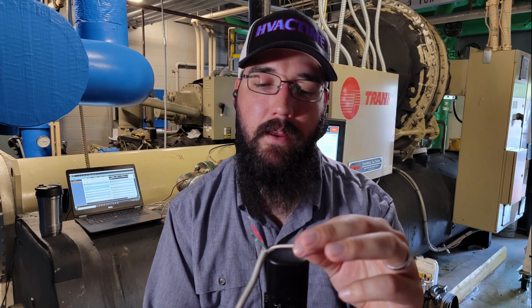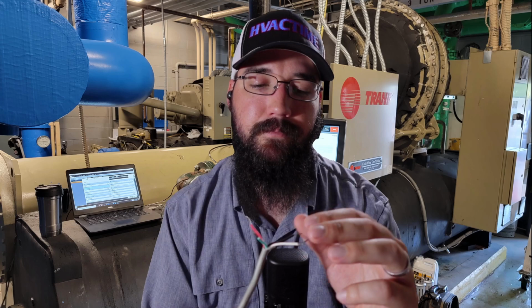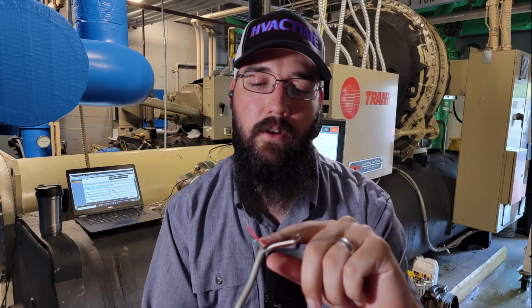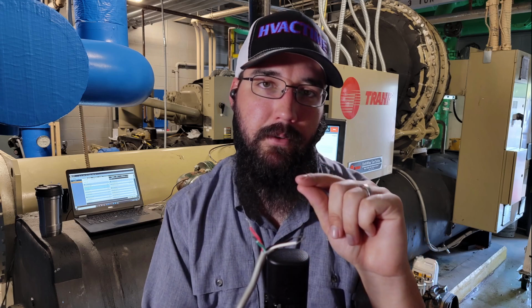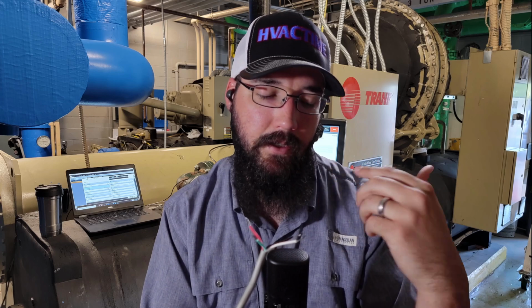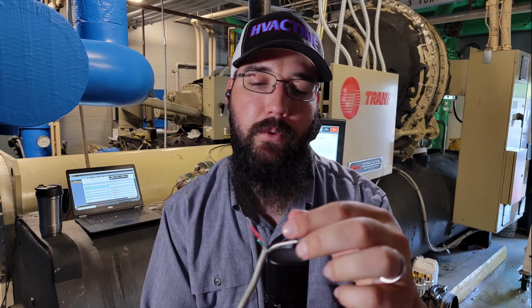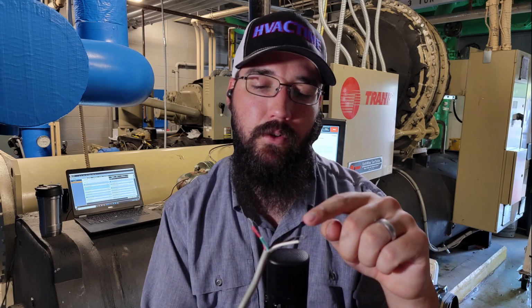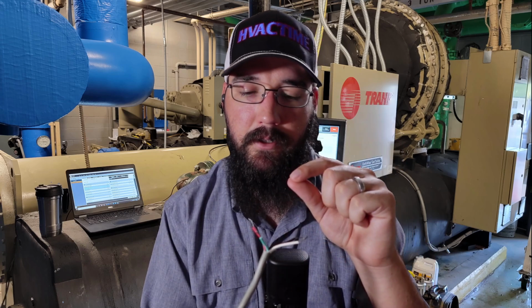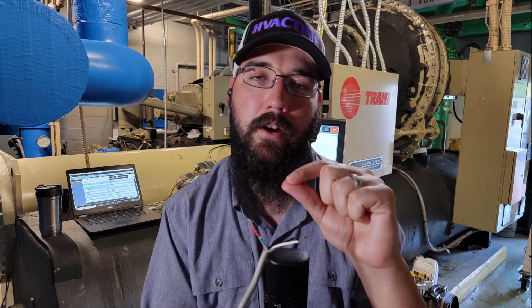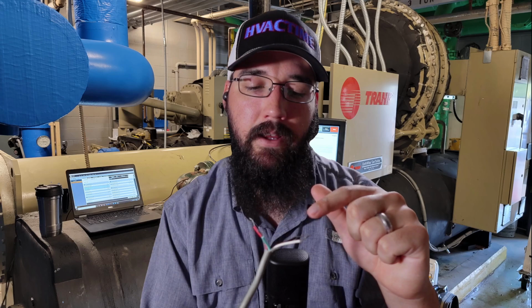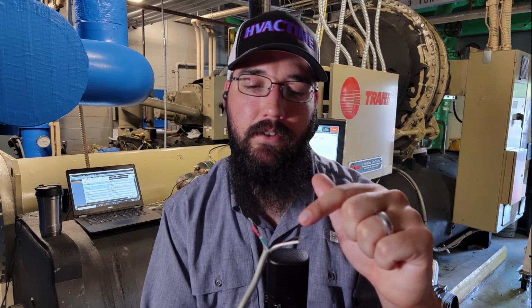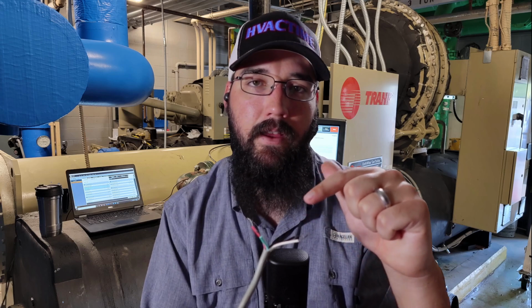Anyway, in a 5 wire example, our 5th wire would be what we would hold as one test pin or test point, and then we would go to each of our other 4 wires. So we'd have, say, a blue 5th wire. One lead would go on the blue, and then we would take the other lead and test to each of these others. And they should all have the same ohm value.